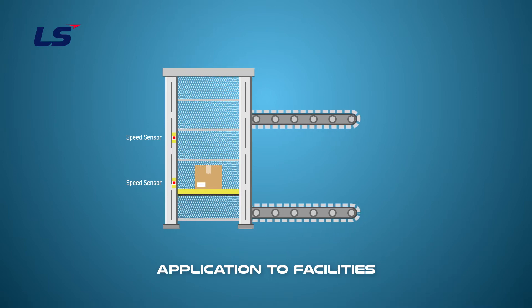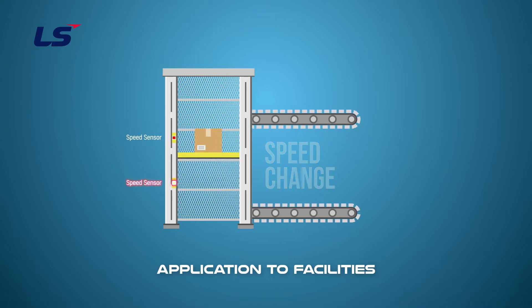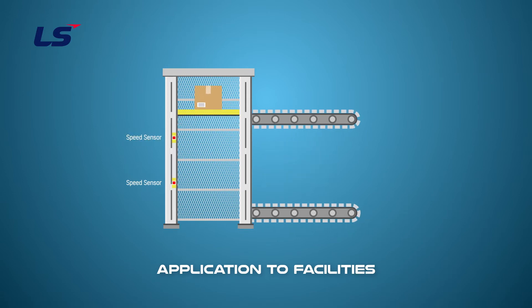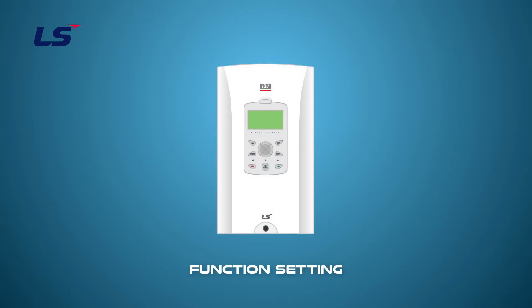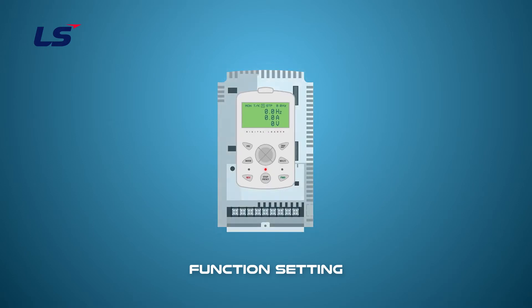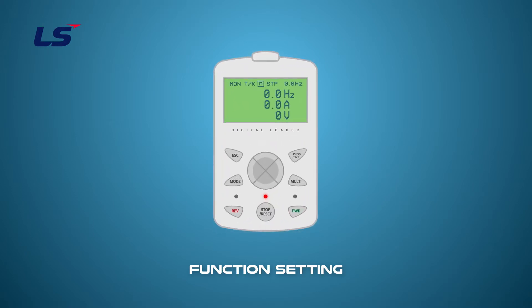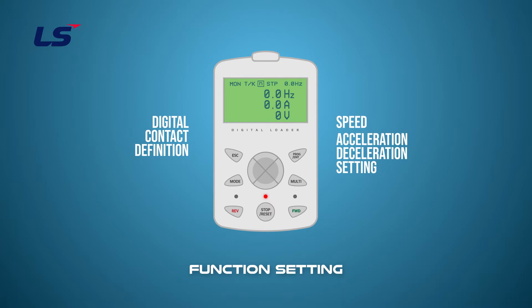The change in speed changes the speed of the motor as the pallet touches the sensor and the contact signal enters the drive. Let's learn how to set up multi-step frequency and multi-step acceleration and deceleration functions. The multi-step control consists of two things: defining multi-function terminals, and speed setting or acceleration-deceleration time setting.